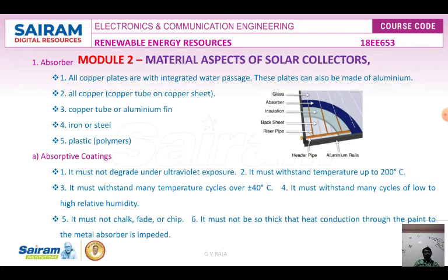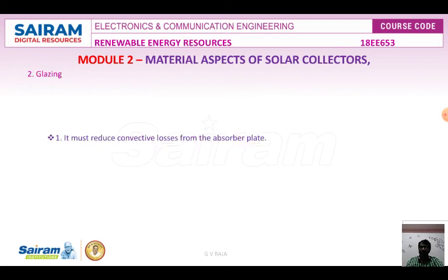The specifications required for the absorber coating of flat plate collectors are: it must not degrade under ultraviolet exposure; it must withstand temperatures up to 200 degrees Celsius; it must withstand many temperature cycles over plus or minus 40 degrees Celsius; it must withstand many cycles of low to high relative humidity; and it must not chalk, fade, or chip.